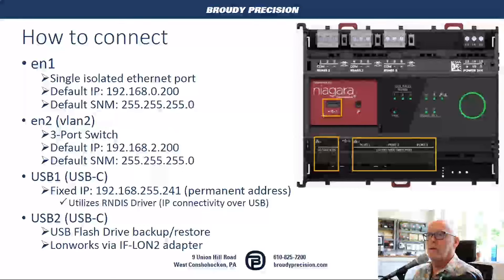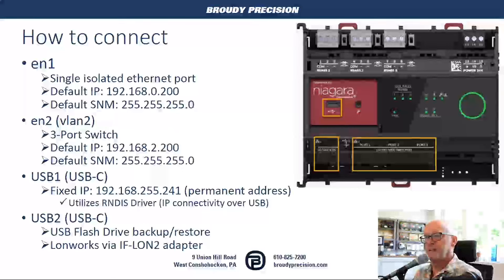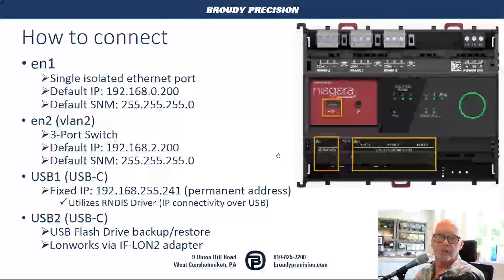There's also a third port, USB1, which is a USB-C connection with a fixed IP address. So even if you don't know what the IP addresses are for EN1 and EN2, you will always be able to connect via the USB-C connection. It has a fixed address of 192.168.255.241 and utilizes IP connectivity over USB. In your device manager and Ethernet settings, you'll see it uses an RNDIS driver. There's also a USB2 port, which is used for USB flash drive backup and restore, and it is also the connection to the IF-LON2 adapter if you're doing Lonworks integration with your advanced controller.